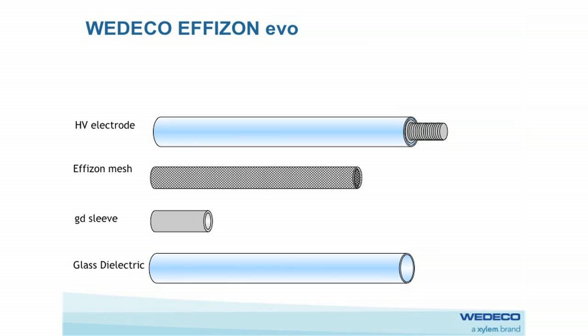What makes Wedeco's system special is our electrode. We have a stainless steel electrode that's covered in a stainless steel mesh and then covered with a glass dielectric. These electrodes are the most robust on the market. They do not need replacing. We've got generators operating in the paper industry that have been operating for about 15 years, producing over 150 kilos an hour of ozone. The shell has never been opened, so those electrodes have never been replaced. Unlike our ceramic counterparts in the market, the ceramic electrodes tend to be consumables.